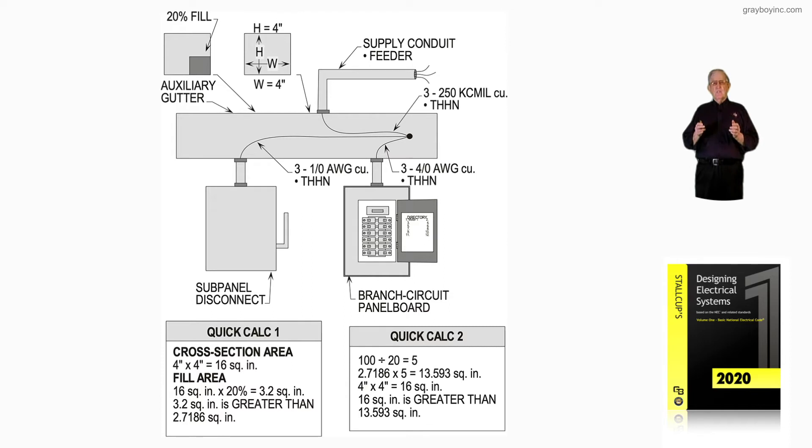We are tapping with smaller conductors to the switch and the panel board. So that means 240.21(B) of the code is being applied here. Notice we have a raceway at the top coming into the top of the auxiliary gutter because it's over 24 inches long. But we have nipples in the taps there. Notice we have three 1/0 AWG THHNs in the subpanel disconnect switch. To the panel board with the main to the right, we have three 4/0 AWG THHNs.